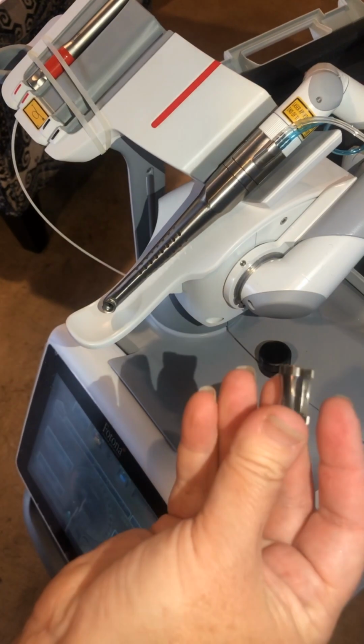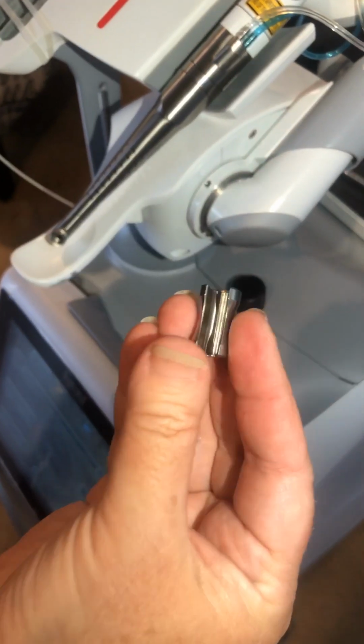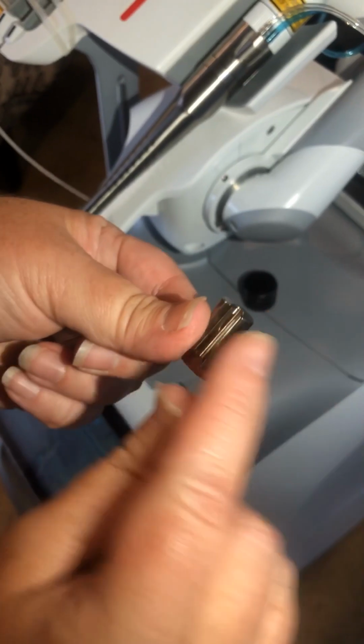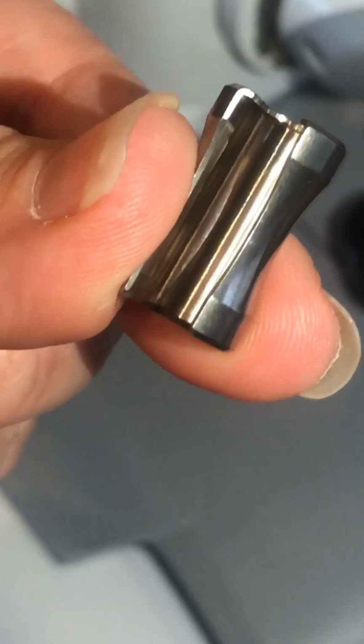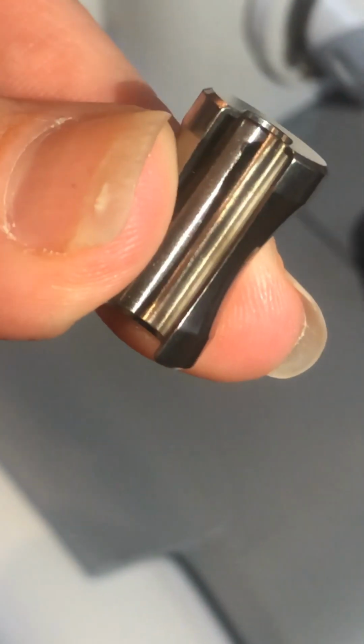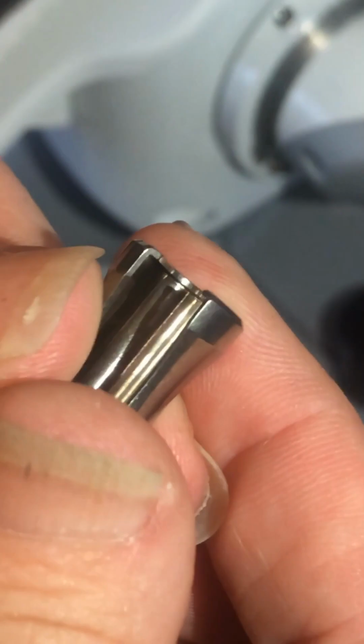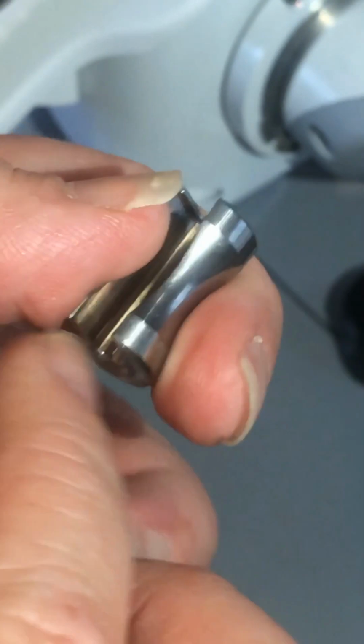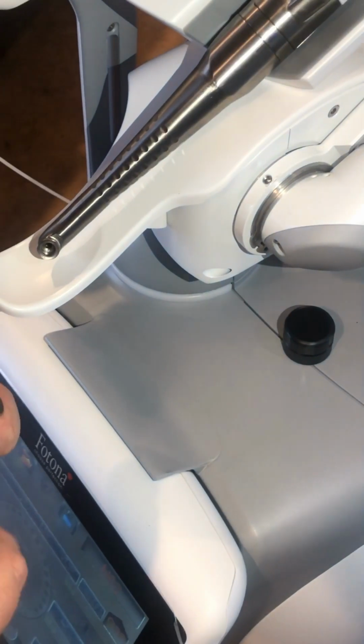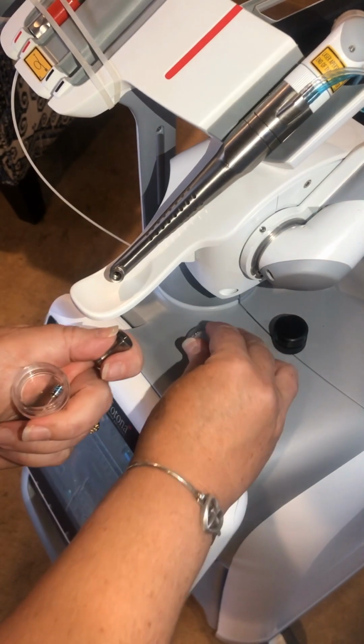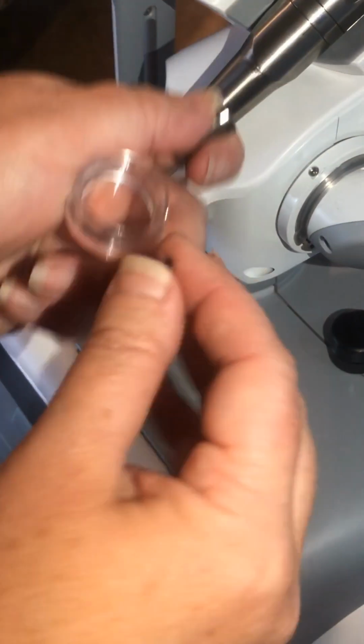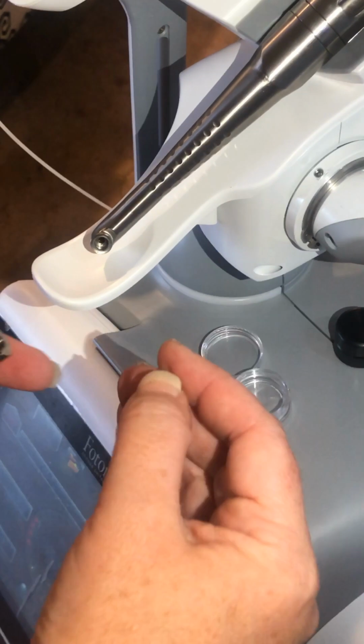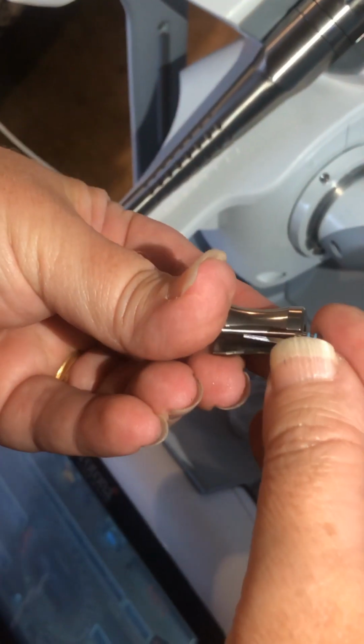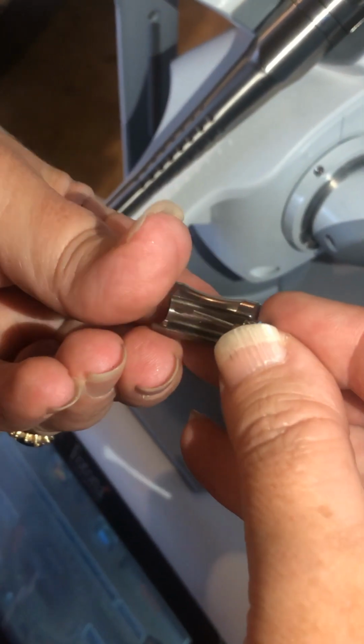With your machine came this little tip changer, and if you look closely, one side has a little trough and the other side is smooth. You see that little trough? That's down on this end here. Okay, perfect. So that trough is where you're going to load the tips into. This is for demonstration purposes only. Normally you would have gloves anytime that you are dealing with tips because the human oils can leave debris.